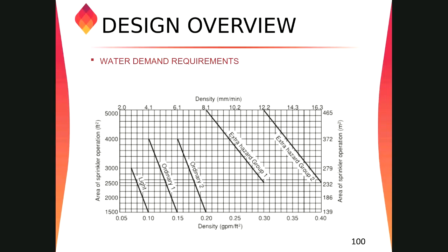So at that one, we need a higher flow requirement. If there is a higher flow requirement, our pump capacity should be of higher value, right? If you multiply 0.40 into 2500, our demand is almost 1000 GPM. Now you see how much the capacity increased, right? 1000 GPM capacity of the flow.